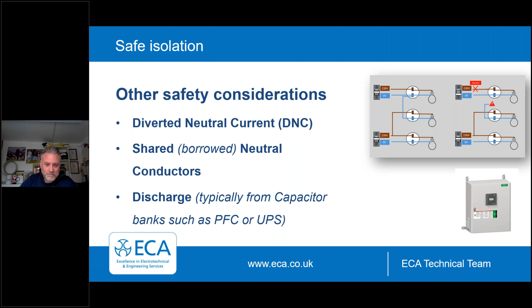So let's look at suitable devices and instruments, and it's really important that we use the right kit. Voltage detectors. So understand that contact and non-contact live circuit detectors are recognised in GS38, and that's a free download from the HSE as well. It's important to stress that these are not to be used to prove isolation, only to prove that something's live. So that is things like your contact pens. The item shown on here is a single pole voltage indicator, and that's a contact device. So your voltage stick is what we call non-contact, and we don't really want to use those. We want to use something that makes contact with the poles.